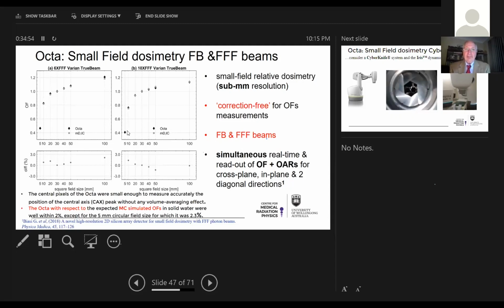You can see here fields from 5 millimeter up to 50 millimeter, comparison with micro diamond and ionization chamber. The ionization chamber can't measure the 5 millimeter field, and we're getting brilliant agreement with micro diamond, but without any of the corrections required for micro diamond. You can see it for the 10 megavoltage field, for the 6 megavoltage field, it's an extremely interesting development. We're getting within 1.5% agreement without any correction.